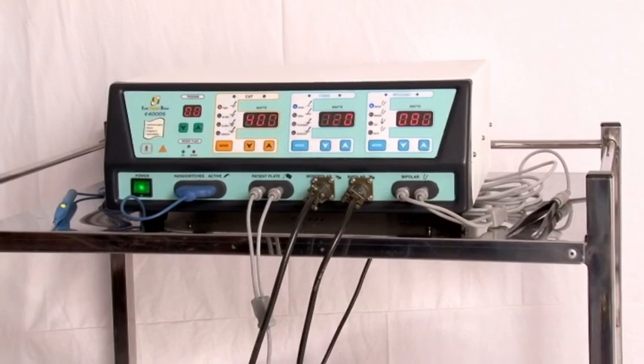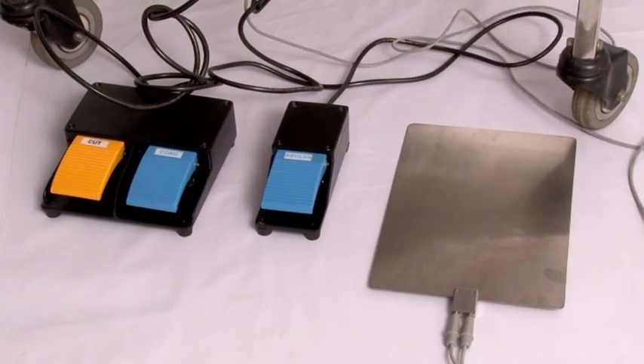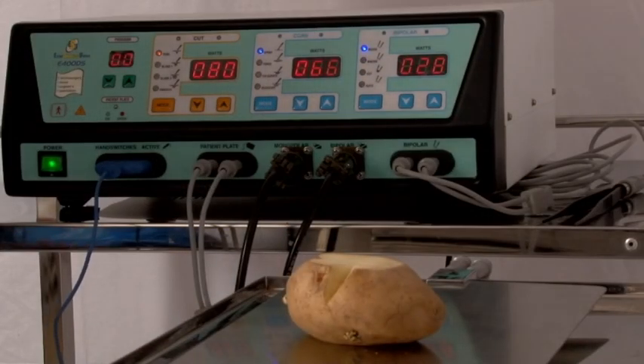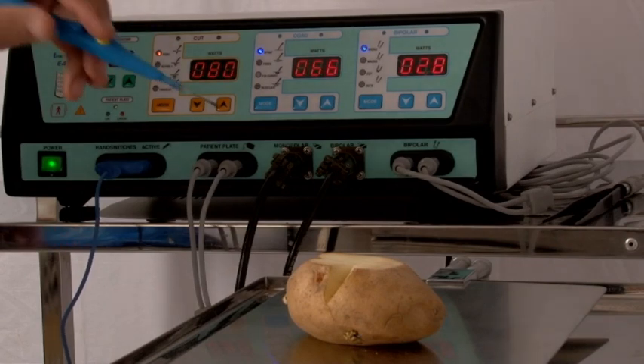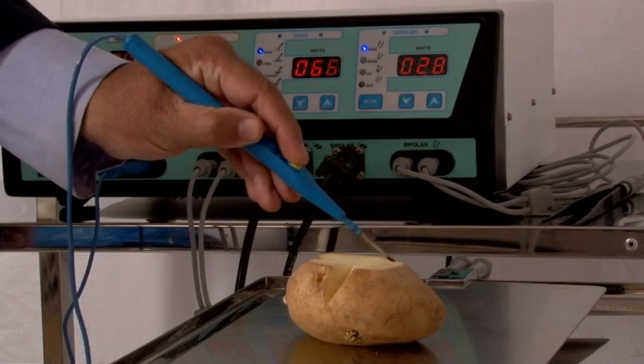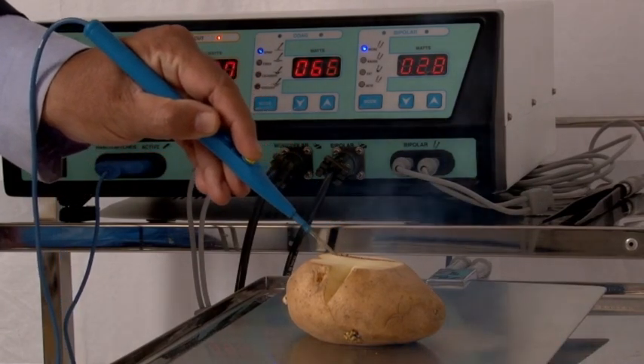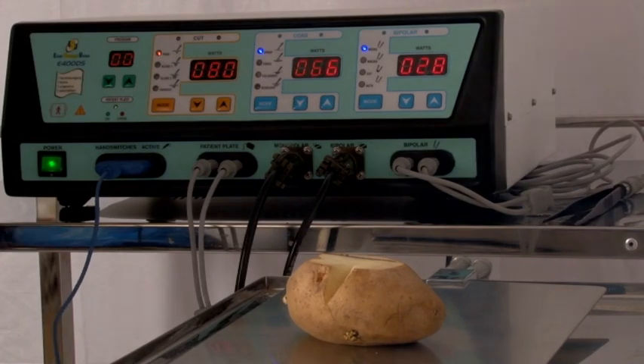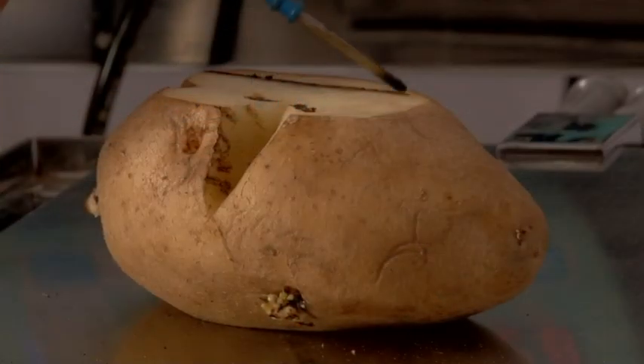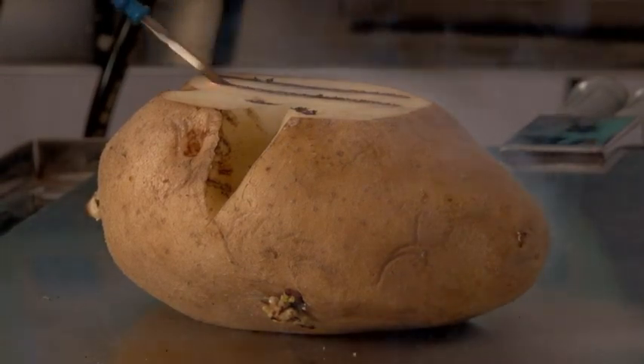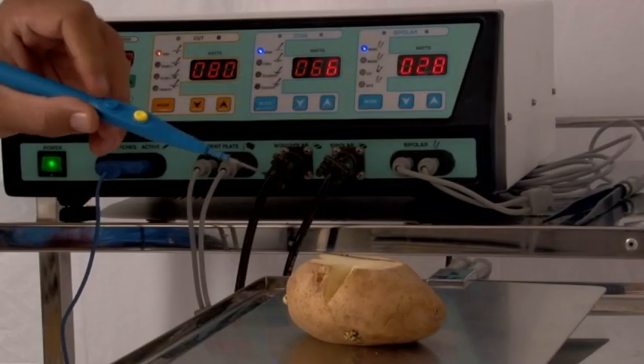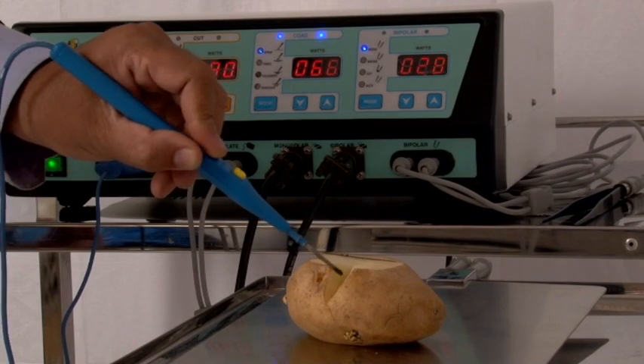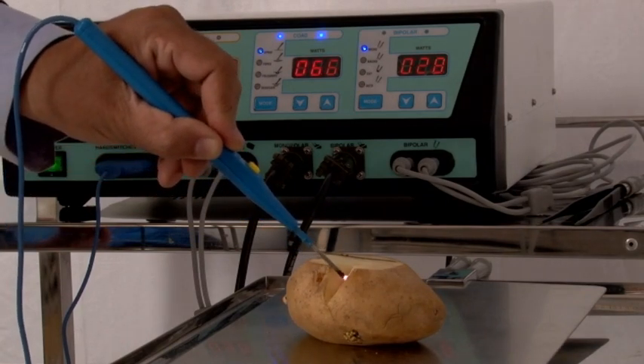Now the electrosurgical unit is ready for surgery with all accessories attached to it. In monopolar mode, we can operate machine with hand switch pencil. When machine is operated in cut mode with yellow button on pencil, it cuts smoothly without dragging effect. We call it a knife in butter effect. In spray coag mode with blue button on pencil, surgeon can spark an arc from a distance without touching the tissues.